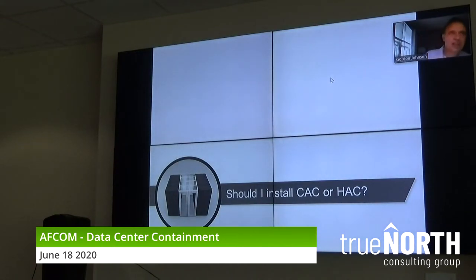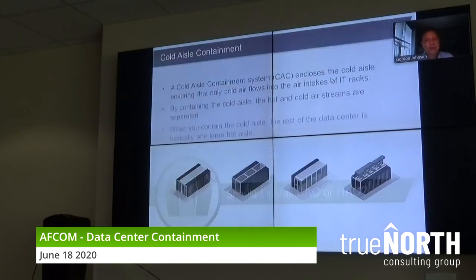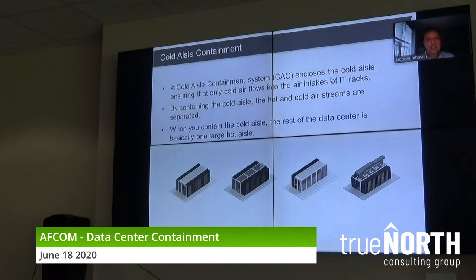And a lot of these questions are almost topics in themselves. Should I install cold aisle containment or hot aisle containment? We get that question quite a bit, and the answer is it depends. First, let's talk about cold aisle containment, and then we'll explain why that answer, it depends, is true. Again, looking just at that third bullet point, when you contain a cold aisle, the rest of the data center is basically one large hot aisle.